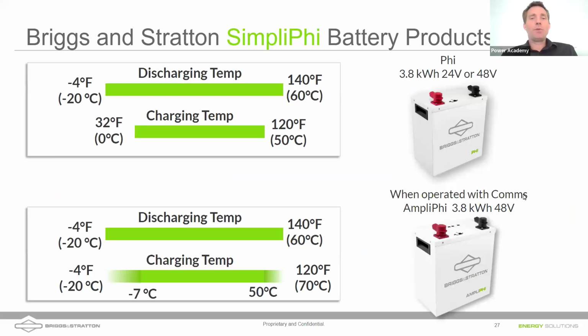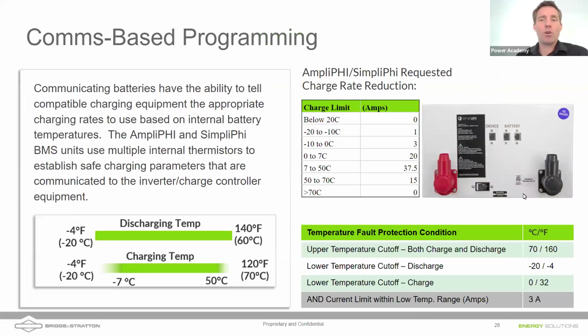So there are some ways we can address this. One, we want to keep our batteries within the safe charging and discharging temperatures, shown on screen for the Phi battery. The AmpliPHI and SimpliPHI batteries have a more advanced BMS with communications, and they can actually charge at temperatures all the way down to -20°C. We just reduce that charge rate, and those batteries will request to be charged at safe levels.